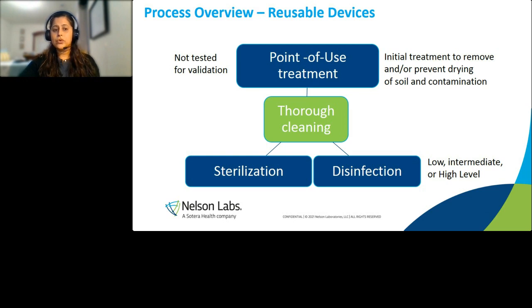But we do go through this entire process, but the point of use treatment usually is not used in the validation. And we go straight to thorough cleaning, sterilization, and disinfection. Today, my point of focus is just on the cleaning validation, but we do perform disinfection validations and sterilization validations. They are not in conjunction. They are performed separately, as their end results are different.